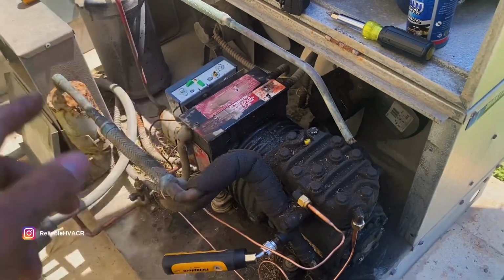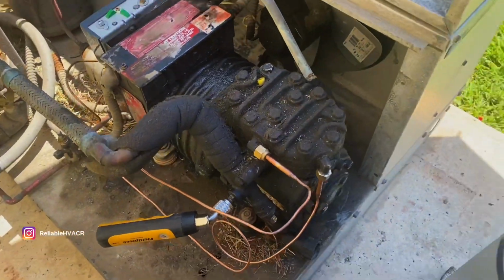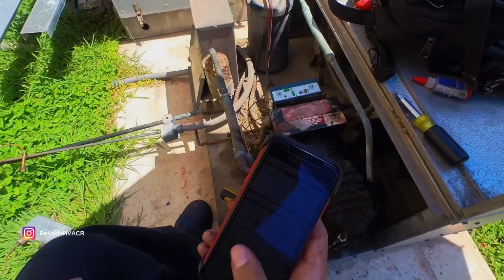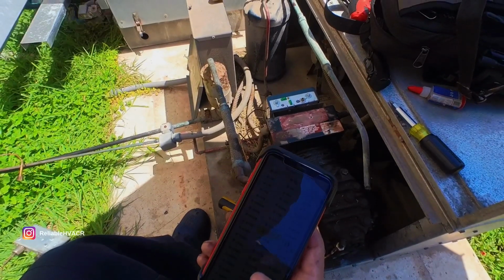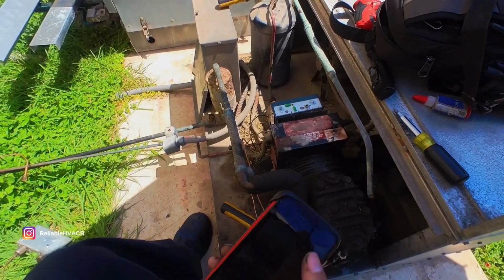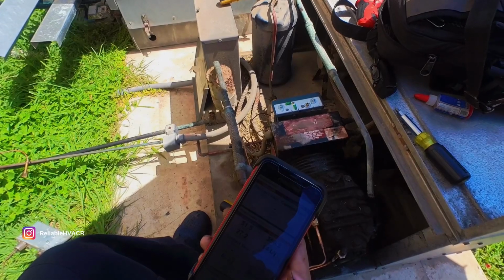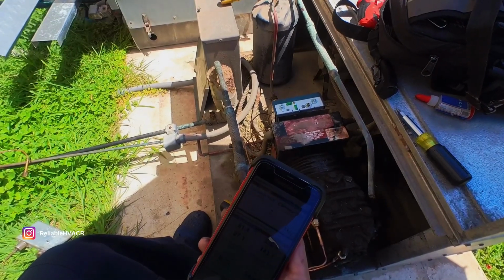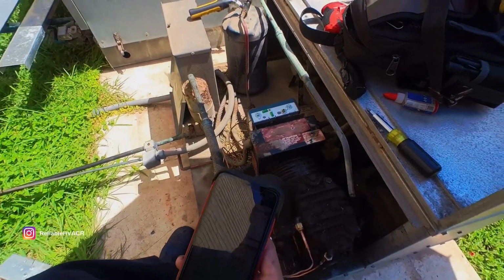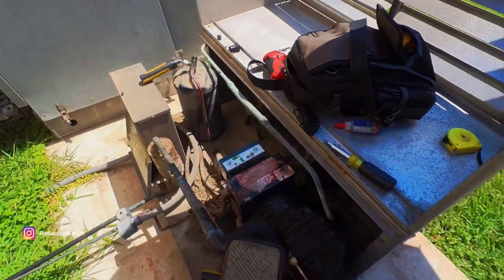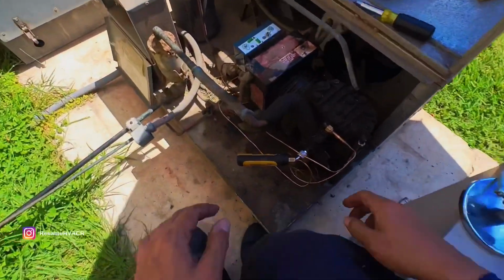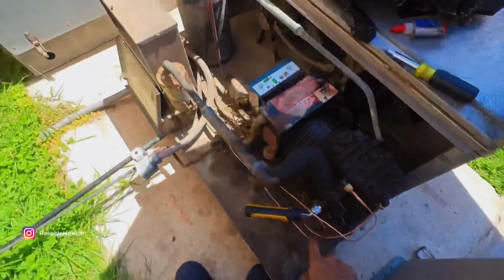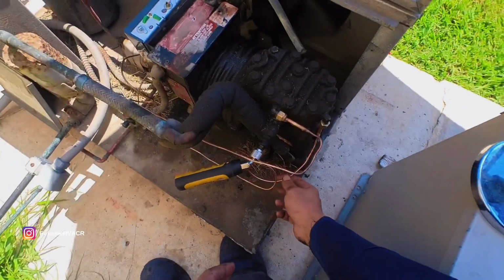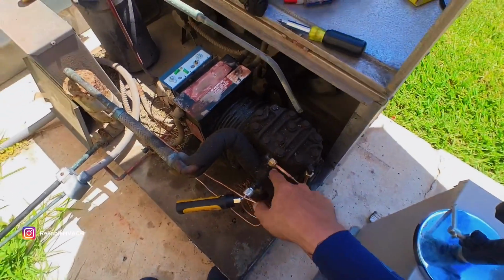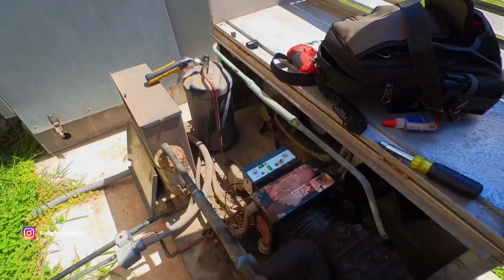Open it up, let all the refrigerant back in, and we should be done. Yeah, it's really high, I'm gonna let it run for a little bit. You see all this vibration - if you leave it touching something, it's gonna rub out and leak. I was checking for leaks here, everything's good.